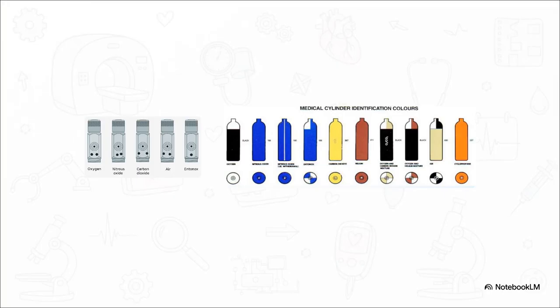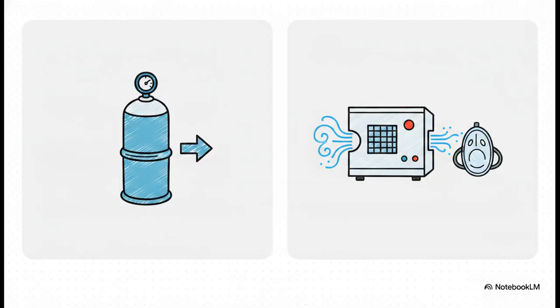Now, hospitals are full of various, sometimes highly dangerous gases, like pure oxygen, nitrous oxide, and carbon dioxide. To prevent a catastrophic mix-up, engineers came up with the pin index safety system. They use specific pin configurations matched with strict color coding, like white and black for oxygen, depending on where you are in the world. These unique pinholes make it physically impossible to accidentally hook up the wrong gas cylinder to a patient's breathing tube. It's just a brilliant, foolproof design.